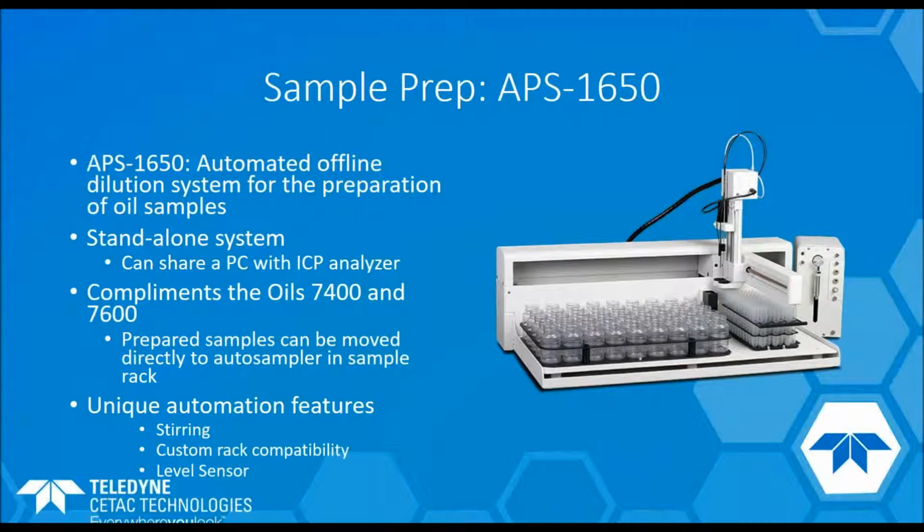In addition to that, we do have specialized pour-off racks for this that use small 2 milliliter vials. The rack is designed such that you put the vials in and you pour in your samples, and if you over pour, it's okay. The racks are designed so that any excess will go to these drip holes that are between the sample positions. Everything drips down into the bottom, which has a little catch tray. So you go prep it on the system, and then once you're done, you dump the little cups and wipe everything down, and it's good to go.